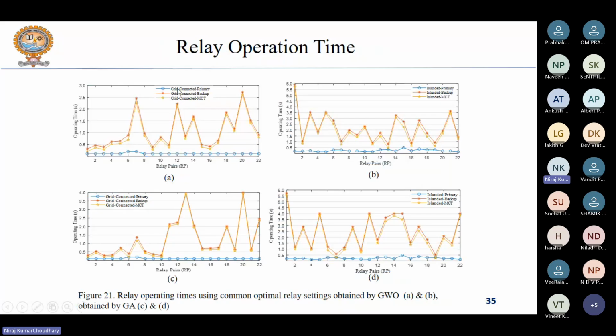So in this particular case, you can see that in the grid connected mode for the primary relay, the time of operation is shown by the blue curve. Then grid connected mode backup relay time of operation is shown by this red curve. And the measured coordination time interval is basically the difference between the time of operation of the backup relay and the primary relay, that is shown by this golden or yellow curve, you can say that.